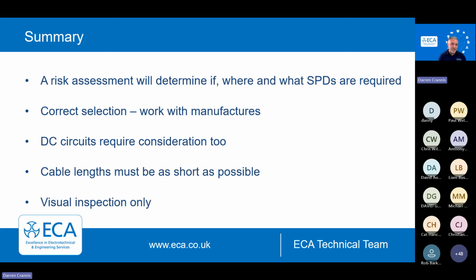Remember that DC circuits need protection too, so that might be built into the equipment, or you might have to look at separate DC SPDs for those. Make sure we keep our cable lengths as short as possible, and if you do have to fit retrofits, which can be challenging, you might have to put a remote indicator panel somewhere else on the panel so you can see if it's gone end of life, or if it's red light, green light. And again, it's just visual inspection only on these.